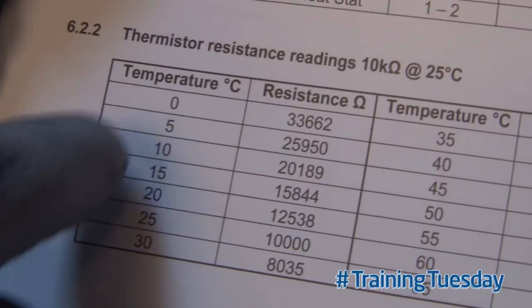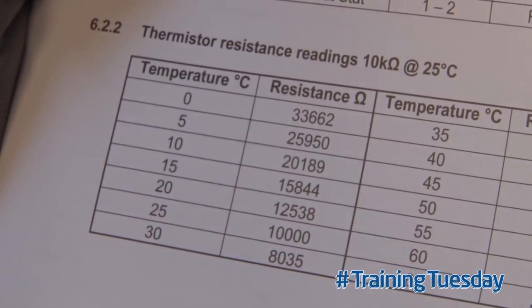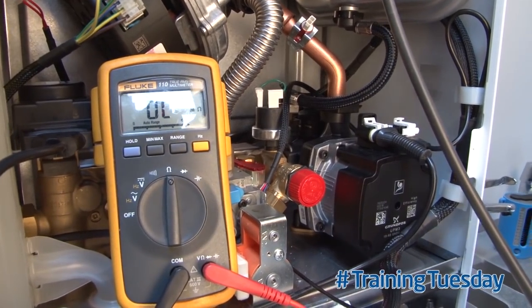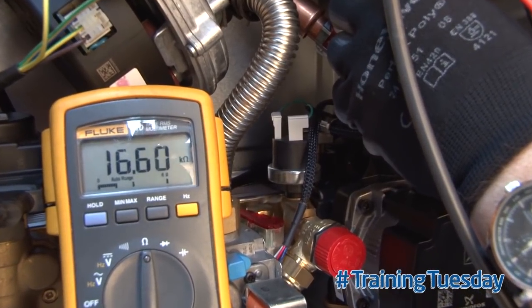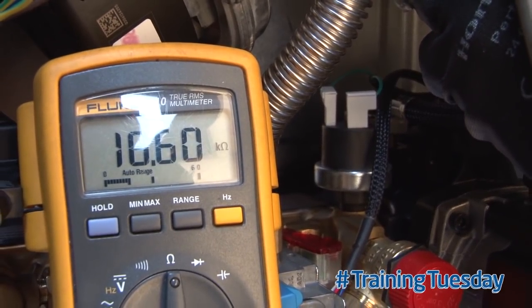The temperature is between 15 to 20 degrees, so the resistance value should be somewhere between 15,000 ohms to 20,000 ohms. We're going to measure that on the thermistor. With a multimeter set to the ohms scale, place the probes across the thermistor and measure the resistance. What we've got is 16,600 ohms, which is within that scale, right in the middle of it.